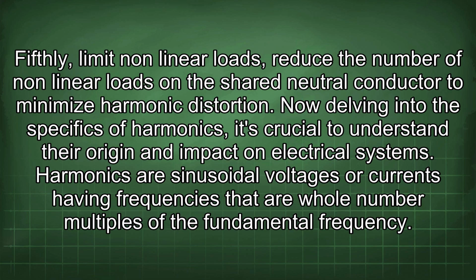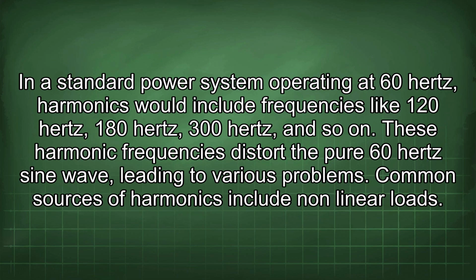Now delving into the specifics of harmonics, it's crucial to understand their origin and impact on electrical systems. Harmonics are sinusoidal voltages or currents having frequencies that are whole number multiples of the fundamental frequency. In a standard power system operating at 60 Hz, harmonics would include frequencies like 120 Hz, 180 Hz, 300 Hz, and so on. These harmonic frequencies distort the pure 60 Hz sine wave, leading to various problems.